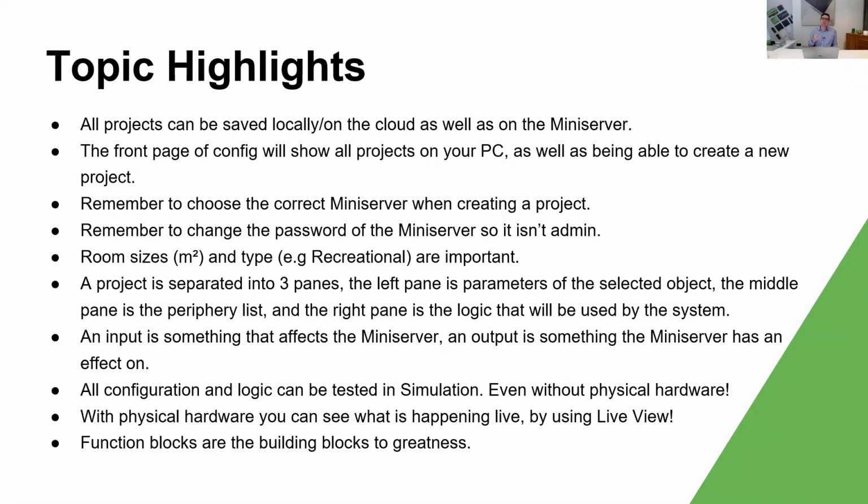Remember to change the admin password. Please, please, please always change the admin password. Room sizes are important and they're in square meters. They're used for heating and cooling logic. The project page is separated into 3 panes: parameters, periphery list, and the page for our config. An input is something that has an effect on the Miniserver, and output is something that the Miniserver affects.